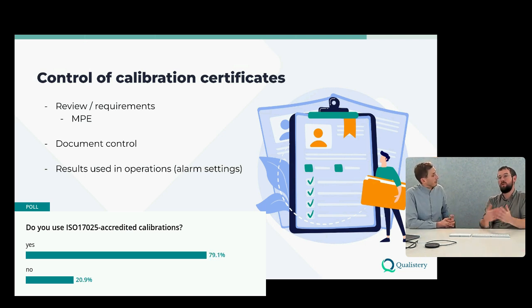Yeah. I think one term that I often tend to sort of set in stone is that both an accredited calibration and a non-accredited calibration can both be traceable. An accredited calibration must be traceable, otherwise it's not accredited. But for accredited calibrations, the accreditation really comes down to trust and being able to prove and document that the calibration activities have been performed in accordance with ISO 17025.